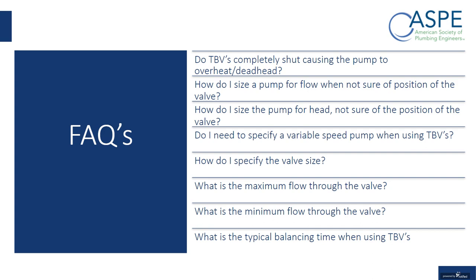What is the typical balancing time when using thermostatic balancing valves? Typically, systems will basically balance in around 2 hours. I just had, about a month ago, a contractor call me up and was excited because his system balanced in 20 minutes. The whole system was probably about 30 balancing valves.